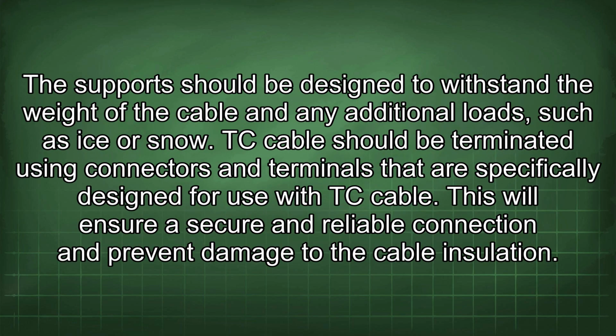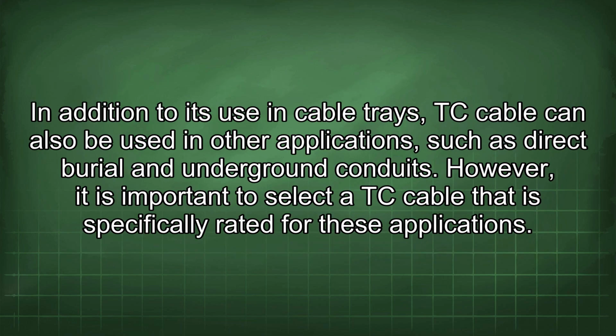The support should be designed to withstand the weight of the cable and any additional loads such as ice or snow. TC cable should be terminated using connectors and terminals that are specifically designed for use with TC cable. This will ensure a secure and reliable connection and prevent damage to the cable insulation. In addition to its use in cable trays, TC cable can also be used in other applications such as direct burial and underground conduits. However, it is important to select a TC cable that is specifically rated for these applications.